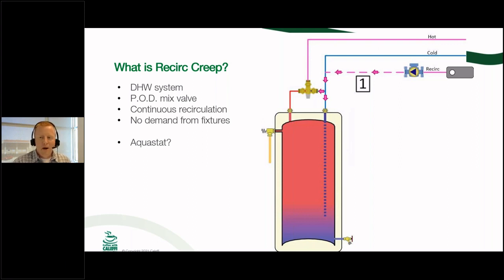Okay, but I want to caution you on that, and I will preface that by saying there are many mixing valve manufacturers that not only recommend but even require aquastats. There are a lot of municipalities as well, certain states that come to mind, California, that require aquastats. And the idea with a lot of the requirements by the AHJs or the local municipalities is that they're trying to save energy. Totally get it. Okay, you want to save energy by turning off that recirc. If the loop's up to temperature, why on earth do we want to keep running that recirc? Okay, but again, there's got to be a trade-off here. There's always a downside. There's always something you got to watch out for.